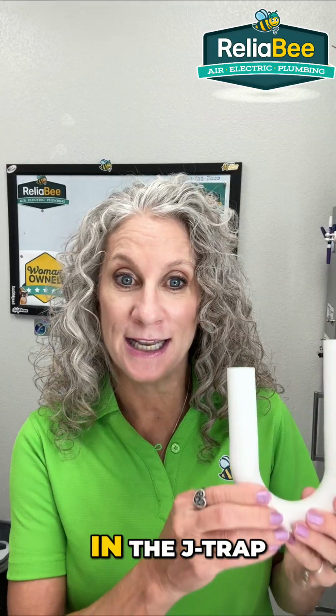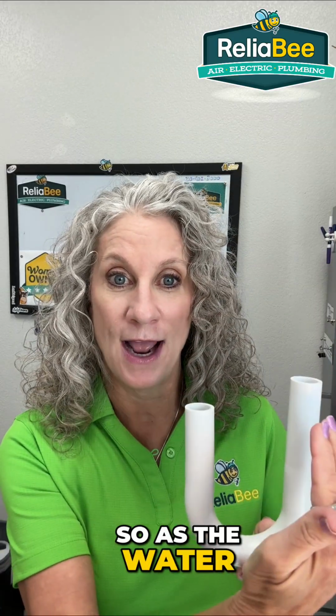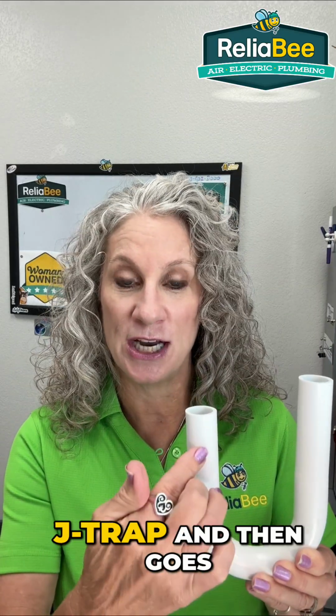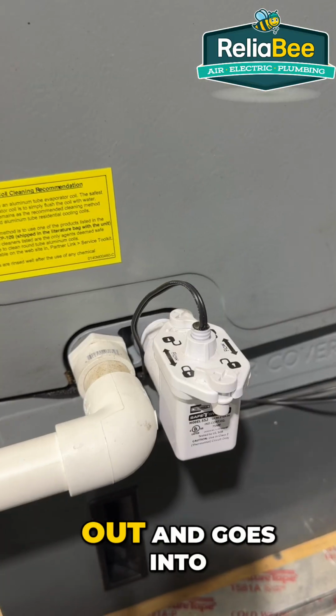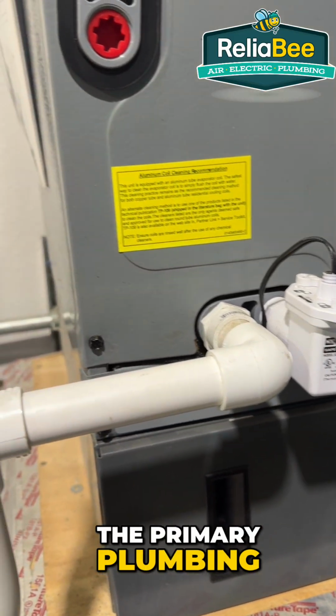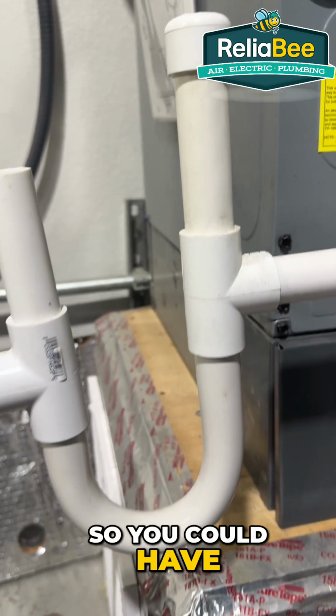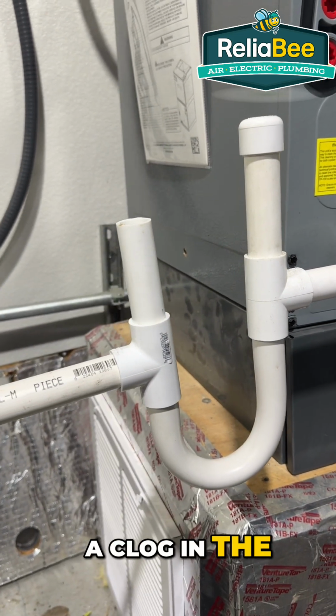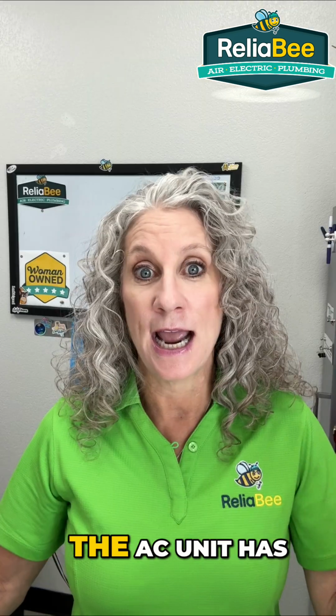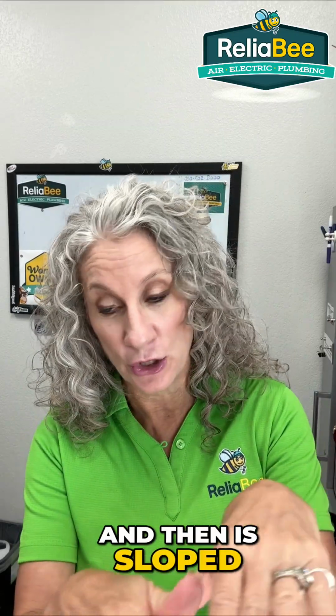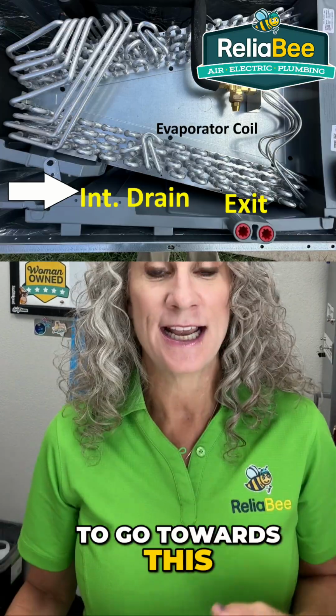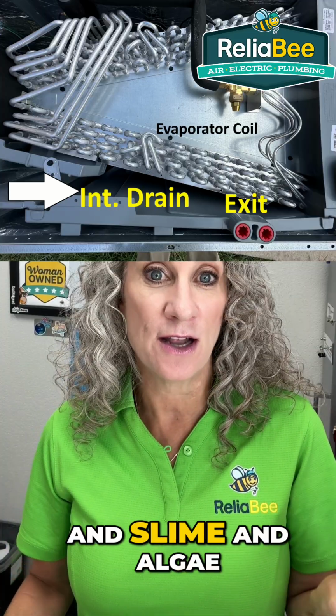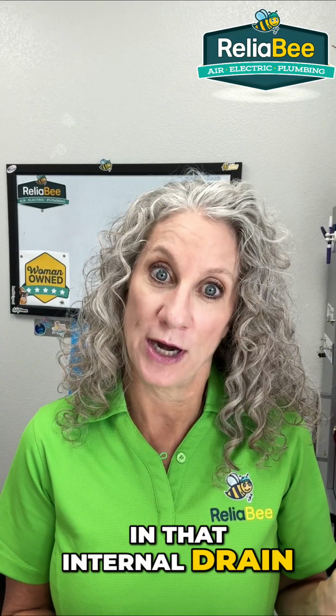So, where can these drain clogs occur? One of them is in the J trap. As the water exits the unit, it goes through a J trap and then goes out into the primary plumbing. So you could have a leak or a clog in the trap itself. The AC unit has an internal drain pan where the water collects and then is sloped to go towards this. You could have sludge and slime and algae in that internal drain pan, which blocks the exit from the drain pan into the J trap.